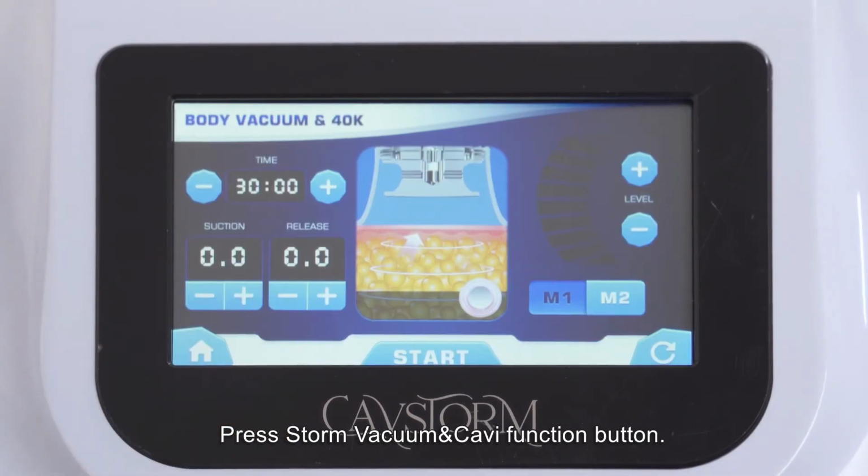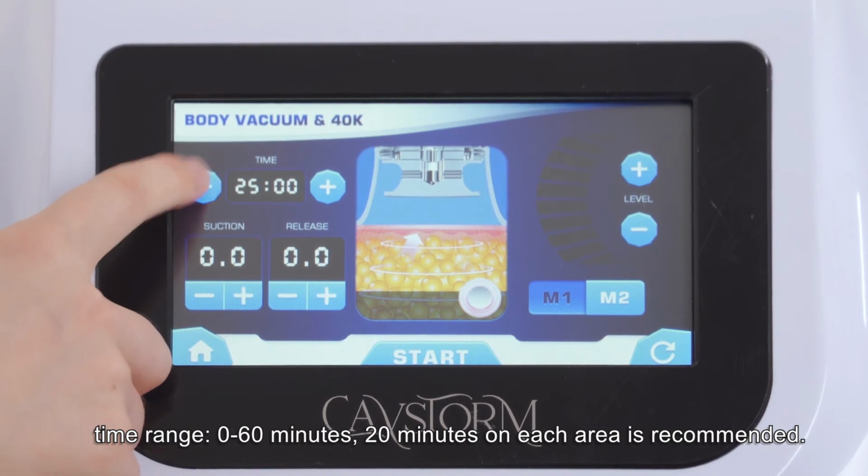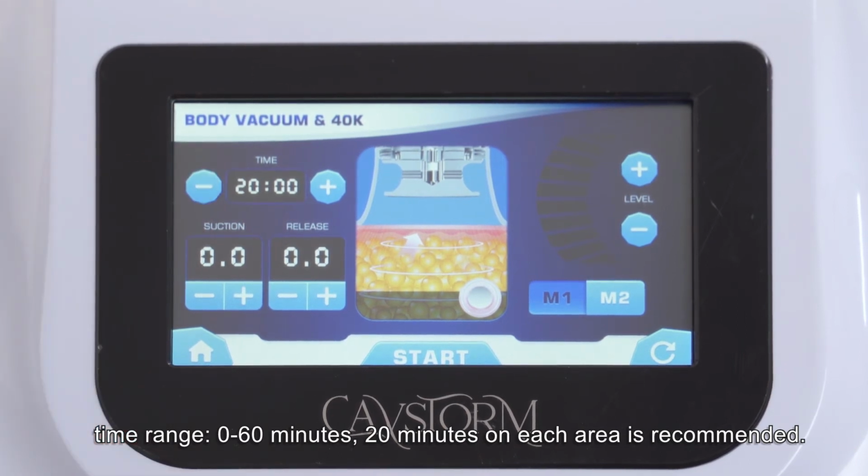Press Storm Vacuum and Cavi function button. Parameter setting. Time range 0 to 60 minutes. 20 minutes on each area is recommended.